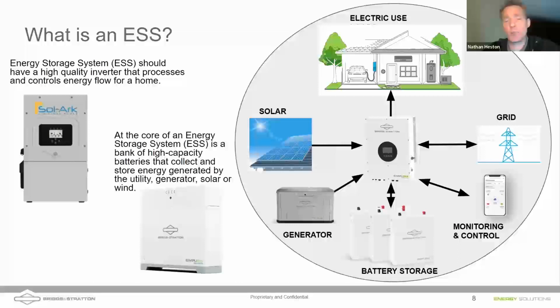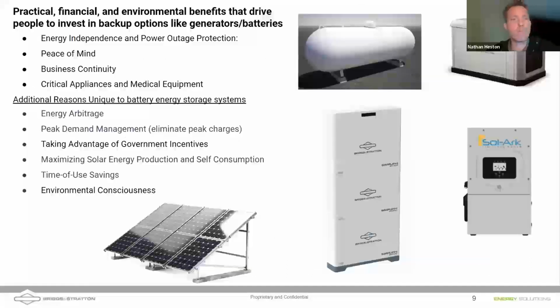Yeah, I think it's a great question. And Russ, if you don't mind, I'm going to postpone until we get to one of these diagrams. But I think the answer is probably going to be an interlocking breaker, potentially an automatic transfer switch. But the problem with an automatic transfer switch, we'll talk about in a little bit, is that you would need to reprogram that inverter. So let's hit that again when we get to a slide where we've got the wiring diagram, so we can make sure that everybody follows exactly what Russ is asking, because we've got one generator or one smart loads input on the Sol-Ark 15k. And of course, if we are on a grid-tied system, then we're already using that grid port, which we could utilize in an off-grid situation for the generator. So let's jump into that later. It's a great question, Russ, and I'll come back to it.